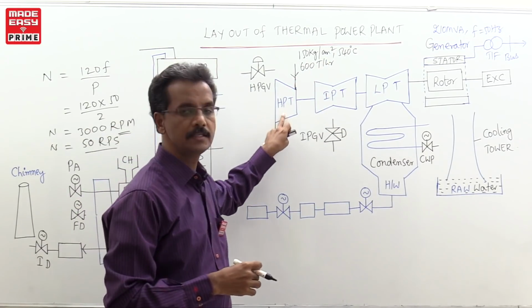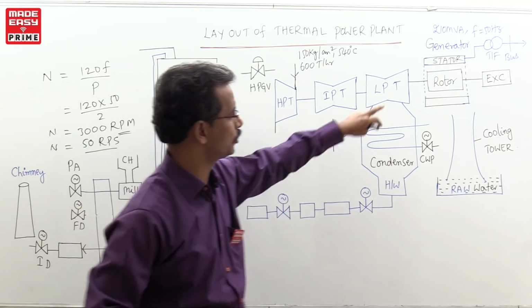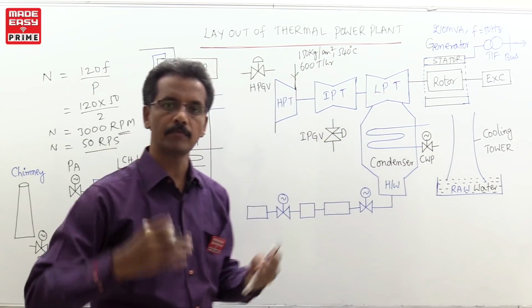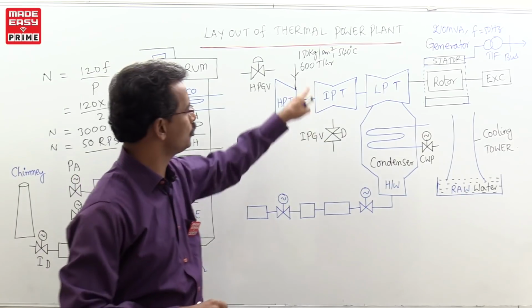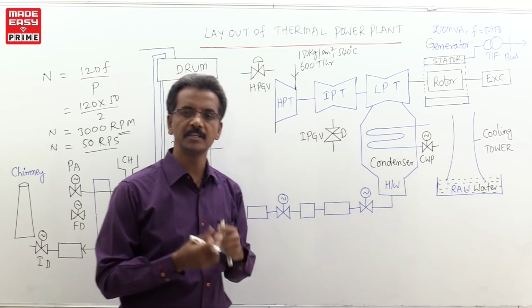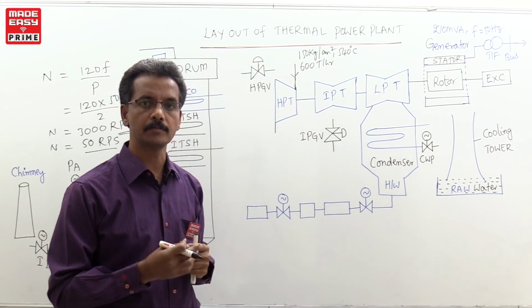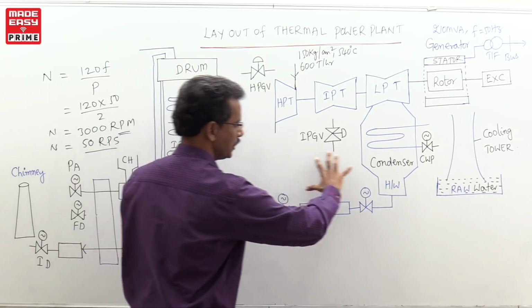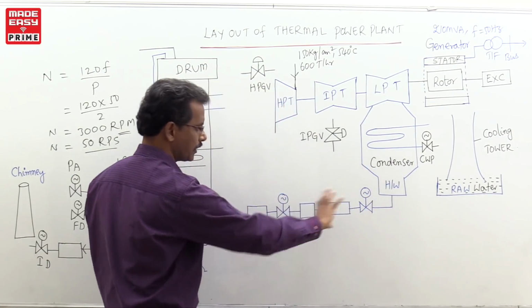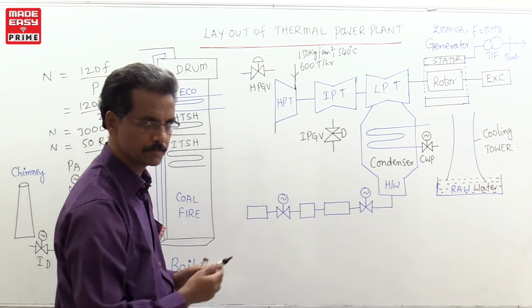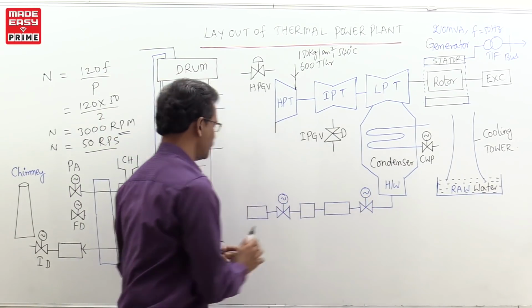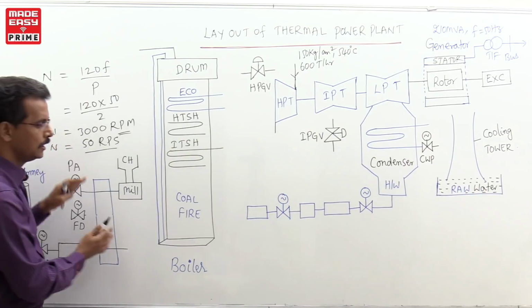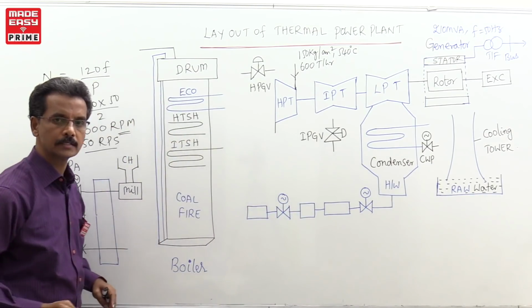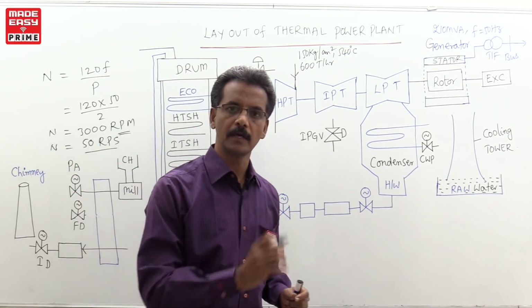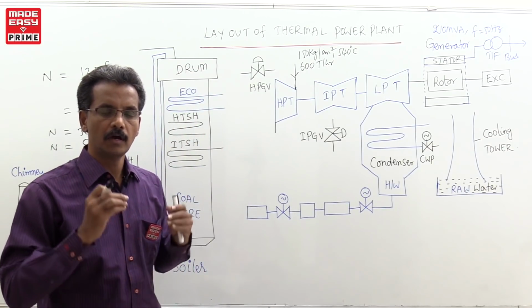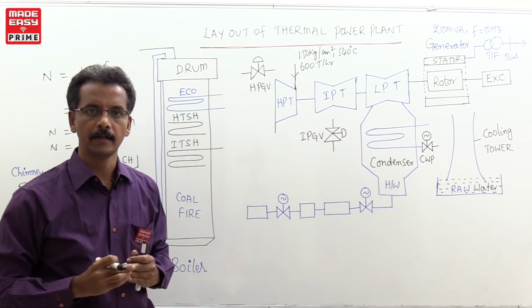150 kgs of pressure, 540 degrees centigrade of temperature, 600 tons per hour of steam flow rate. If you send this inside the turbine, then only can you rotate the generator at a speed of 50 revolutions per second. But how do we get these high parameters of the steam? For that purpose, we are using all these equipments that I have drawn. I have not given the names; now I will fill in the names and you will get the idea. All these equipments we call the auxiliary equipments of our thermal plant. Now I will explain the process of this thermal plant.